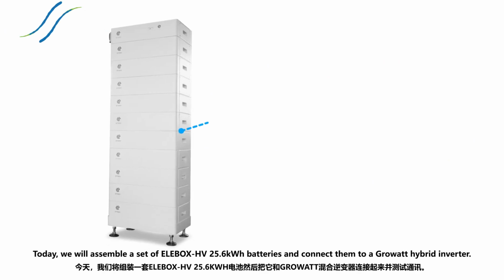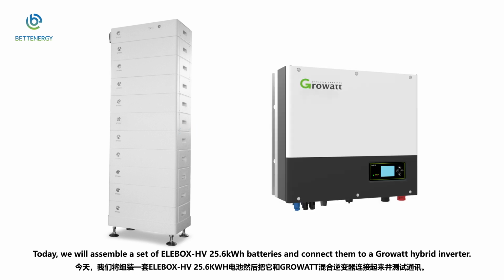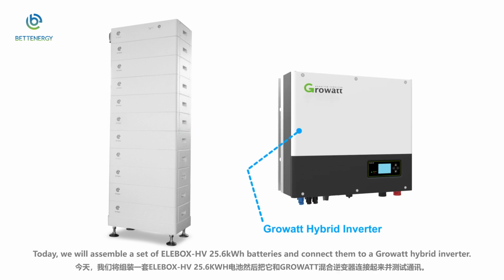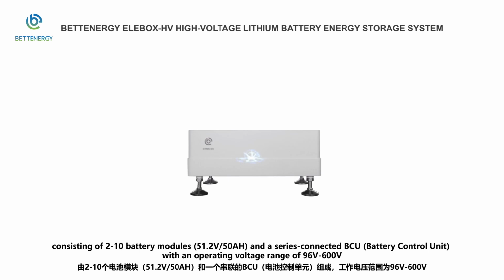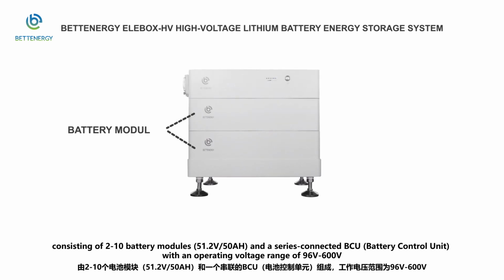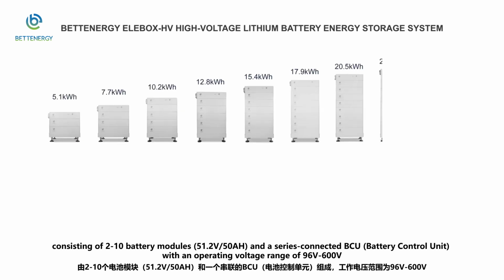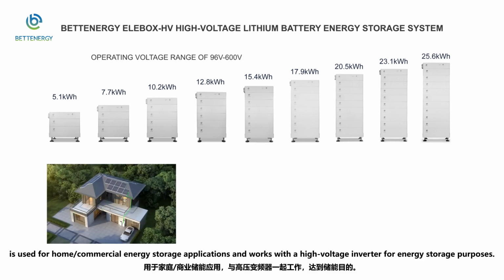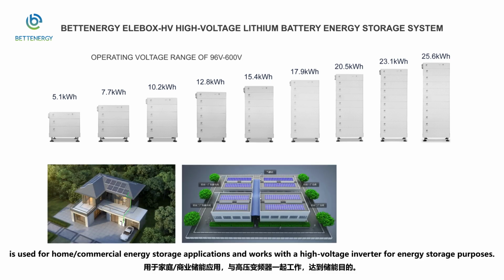Today we will assemble a set of ELEBOX HV 25.6 kWh batteries and connect them to a Growatt hybrid inverter. Bettenergy ELEBOX HV high voltage lithium battery energy storage system consists of 2-10 battery modules, 51.2V, 50Ah, and a series connected BCU, battery control unit, with an operating voltage range of 96 to 600 volts. It is used for home and commercial energy storage applications and works with a high voltage inverter for energy storage purposes.